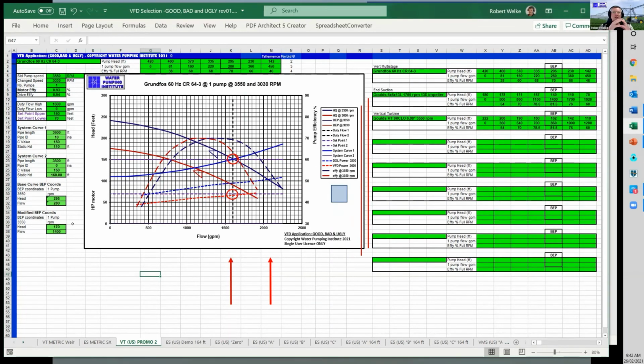So if you're designing a pumping system that needs to operate on a VFD, you can import a pump curve that's around about the mark, and you can massage it. You know, say for the head you want a 250 foot head instead of 170, and it will produce the pump curve at that higher head. Then you can start playing around with it. You know, obviously the static head will be 200 feet. So there's so much flexibility in this software.